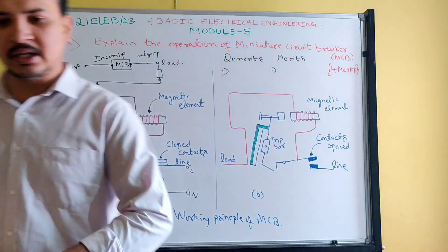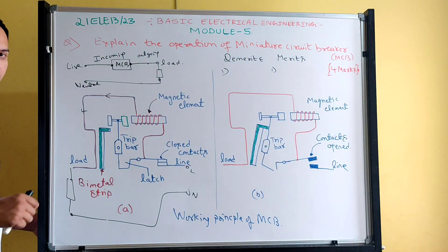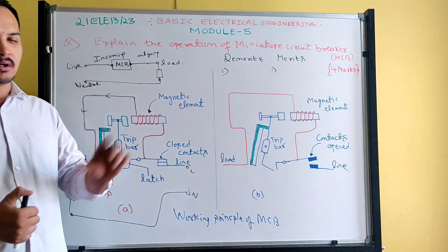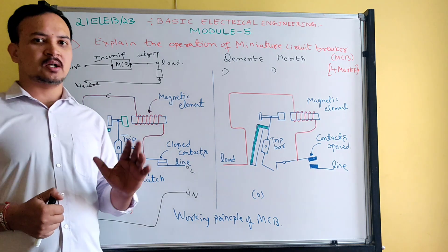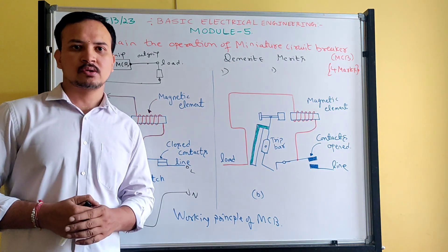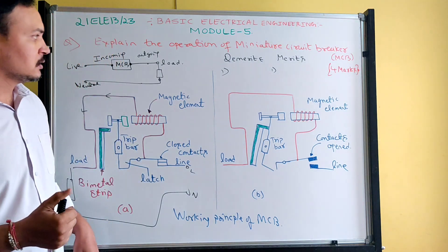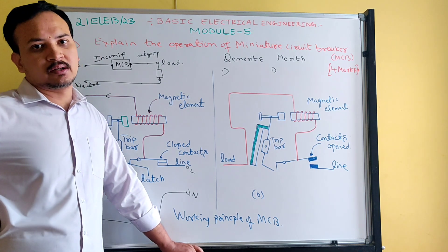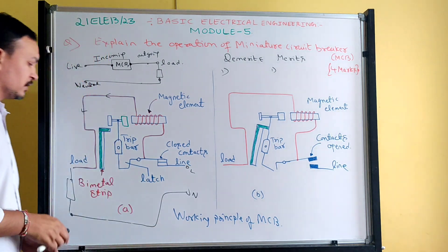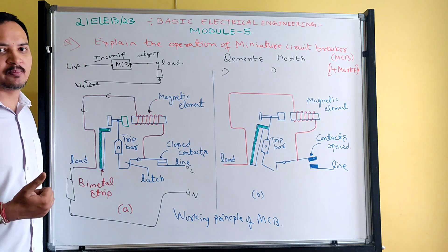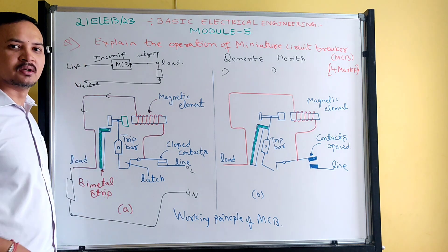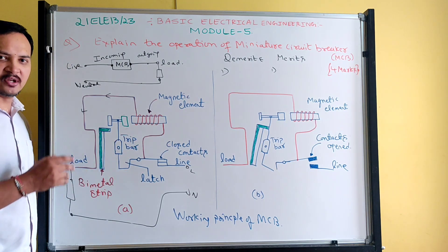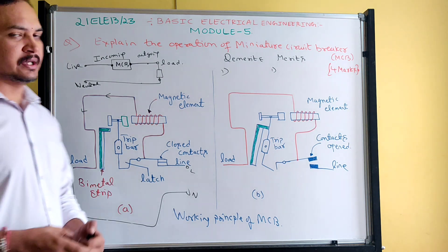Coming to demerits: sometimes what happens is slow tripping. If tripping is slow, due to that slow tripping time, the fault current may damage the load equipment — chances are there. Next is aging factor — aging and wearing. For example, even if a fault occurs, if the latch is worn and does not trip, fault current passes through the load and source — the entire system gets damaged. That is the aging factor.